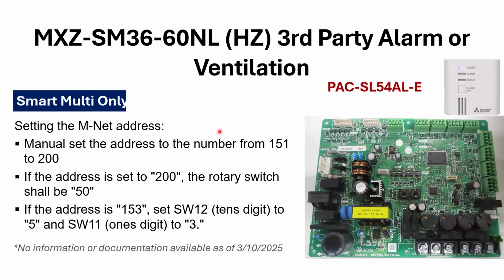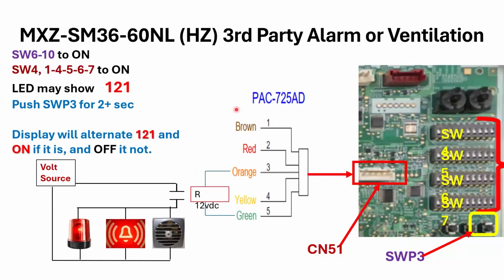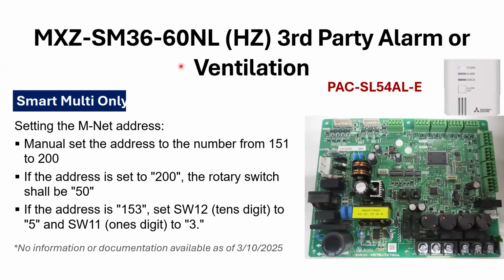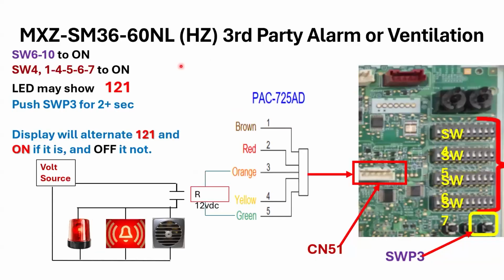So that tells me we got to get MNet wired to it. So that's got to come from the outdoor unit or the branch box. It's going to get an address number. Here's the addressing range, 151 to 200. Let's say the address is 153. Okay, it's just telling you how to set the addressing for that. So again, you're going to need some MNet wiring and connect that off the MNet. And then actually, no, this is a different setup here. So this is an option.